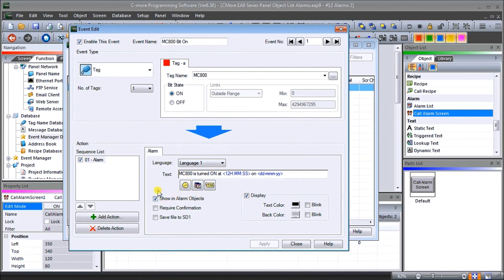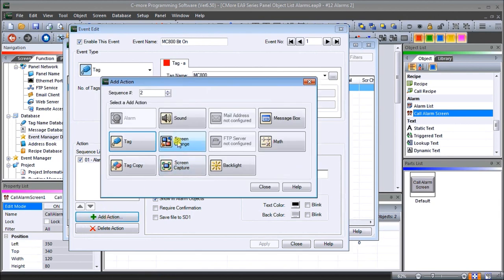We then have the option to show in alarm objects — these are the objects we just programmed on our screen, so they will be shown there. There's also a 'display' option: if you want this alarm to show up on the actual display on every page at the bottom, just hit that button and set text color and background color. Under 'action', it defaults to alarm, but we can add more actions by hitting 'plus action'. Options include alarms, sounds, email, message box, change tags, copy tags, change screens, capture screen, FTP server, math, and change backlight. In this case we're just setting alarms, so let's close that.